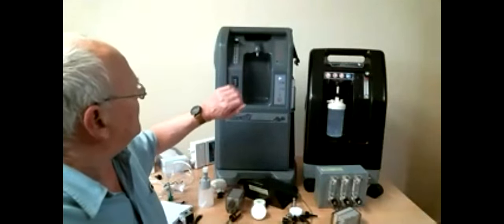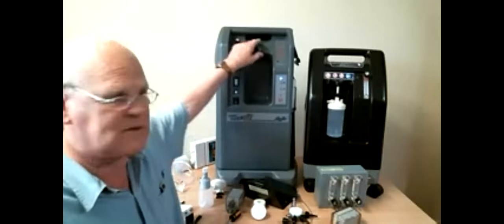And it is important to make sure that you go over it before you start the machine up, and just make sure that the alarms will work if you plug it in and switch it on and then turn the power supply off. Do you get an alarm? Will the clinician know that it stopped working when power fails? So it's important that you just go around the machine, keep it clean, keep it tidy, check the filters, and it should last a very long time. I had an email this morning from somebody that had a concentrator, it had done 37,000 hours, and it was still producing very good oxygen. So they will last, providing they have that little bit of care and maintenance.